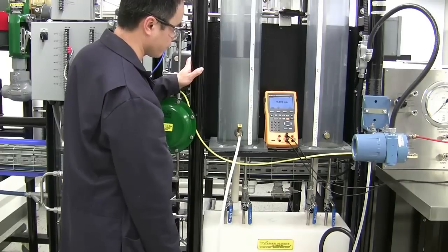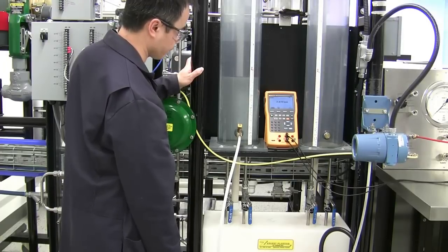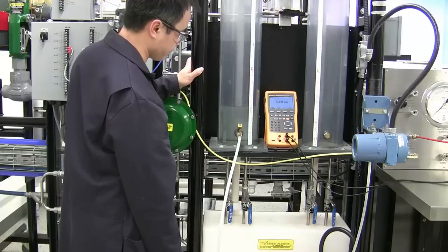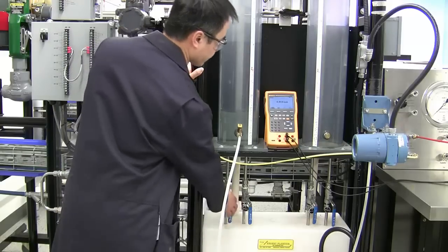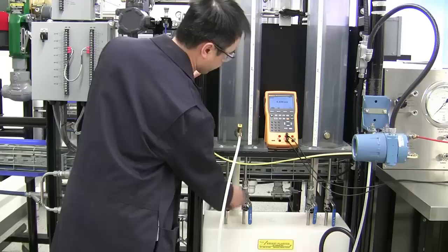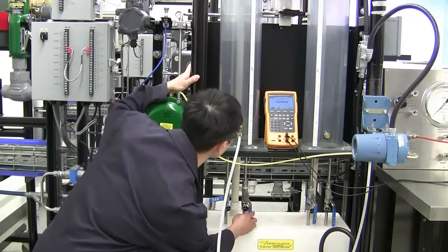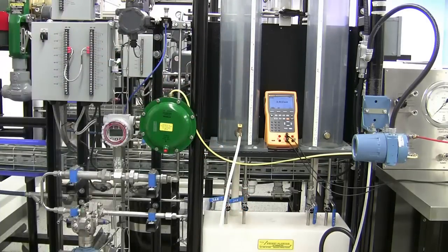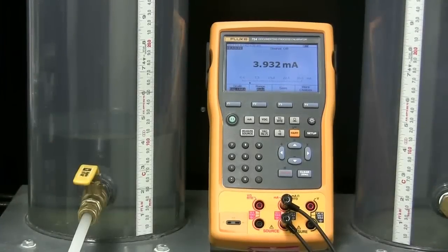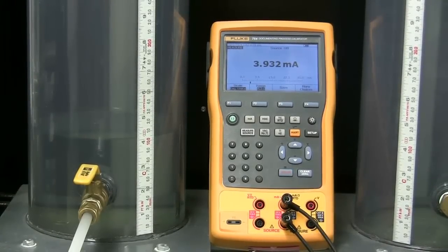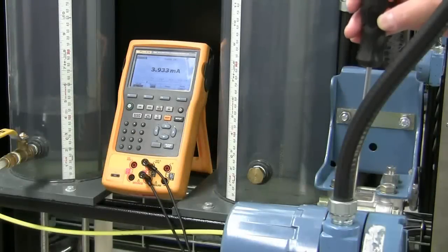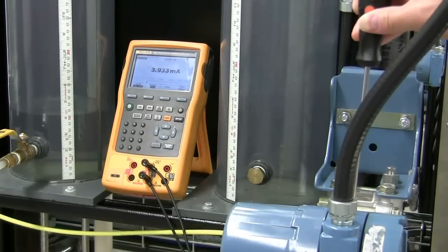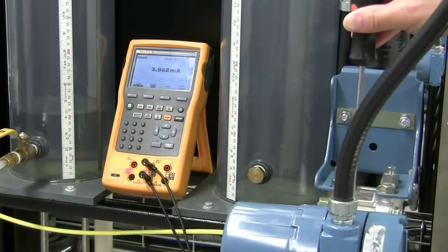Verify the level reading by lowering the water level to 10 cm. At this point the transmitter should be reading 4 mA. If the transmitter is not outputting 4 mA, it could be due to the error in our calibration and the assumptions made earlier. To correct for this error, zero the transmitter at this point.